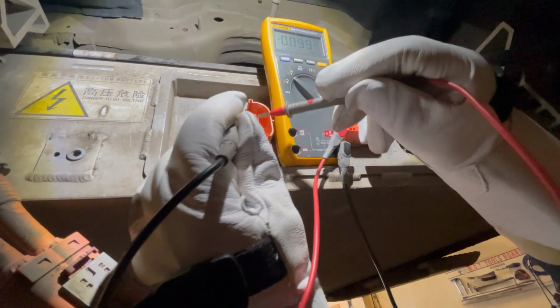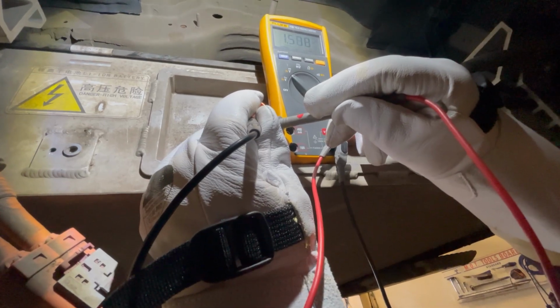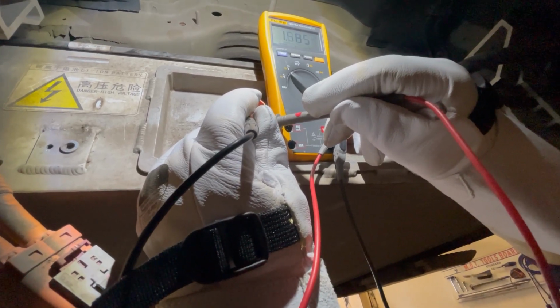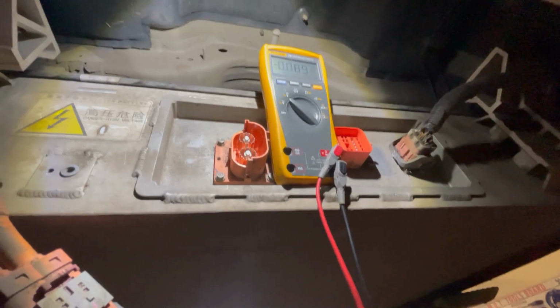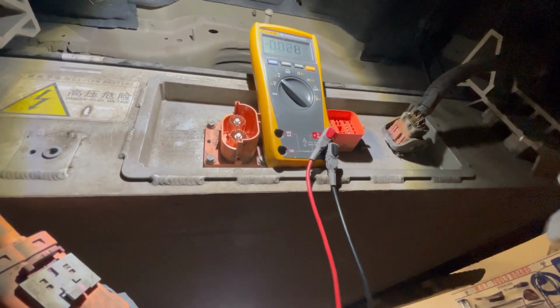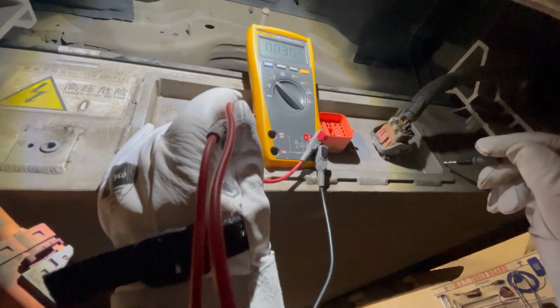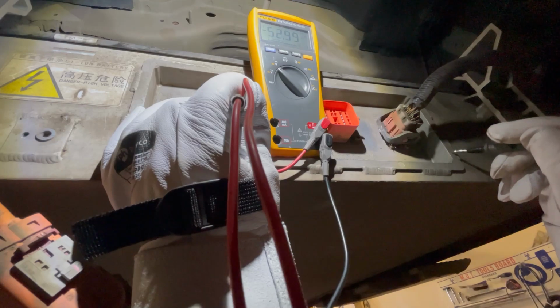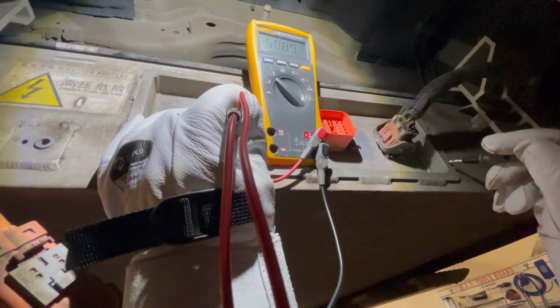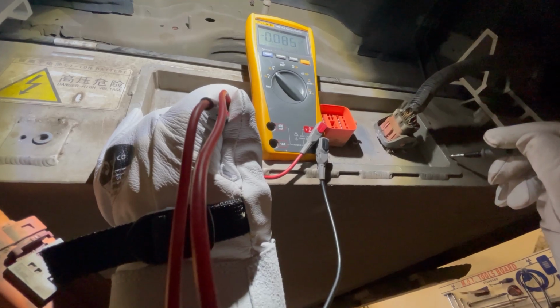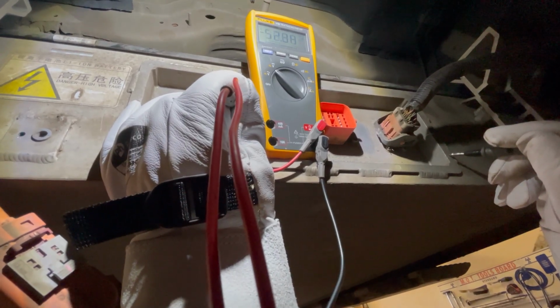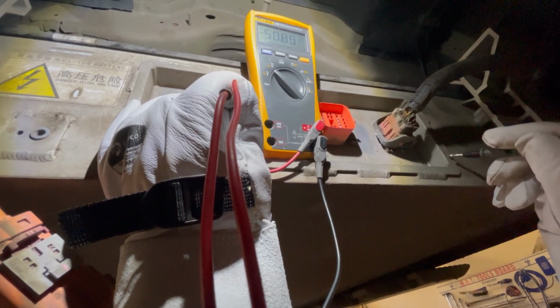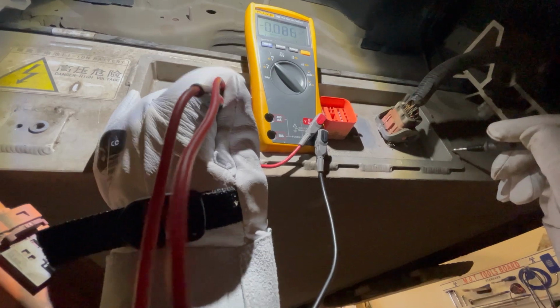And just now we have got 1.5 volts. I'm going to swap the polarity around. 1.5. That's kind of strange, mind you, because it says this is the negative and that's the positive. What is concerning slightly is when I put the black terminal just on the earth of the body and pick up one of the terminals, it's shown that I have got, well, it says there minus 50 volts. I thought we should have had 0 on both. Remember, this battery is damaged, so we don't know if part of the high voltage cable is rubbing against the battery box inside. Nothing there, 50 volts.